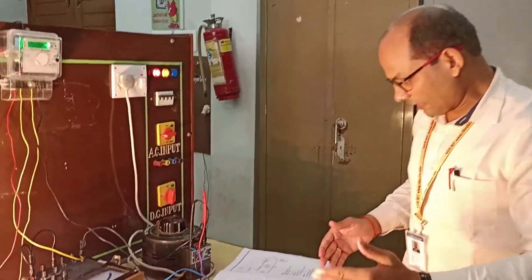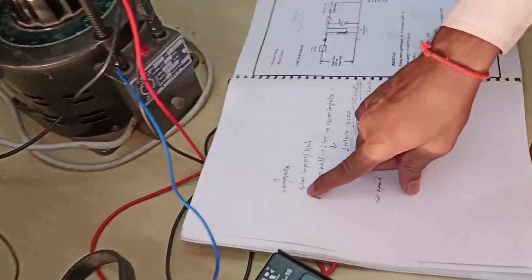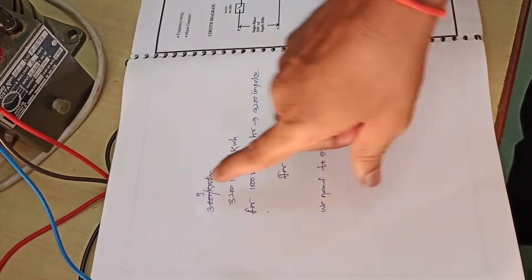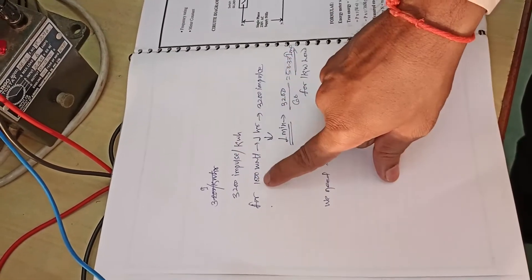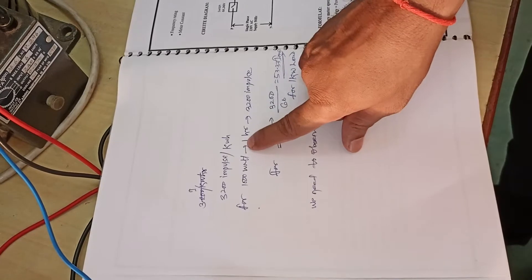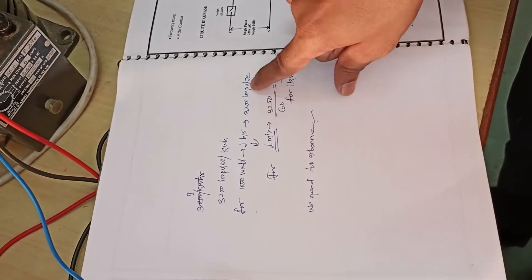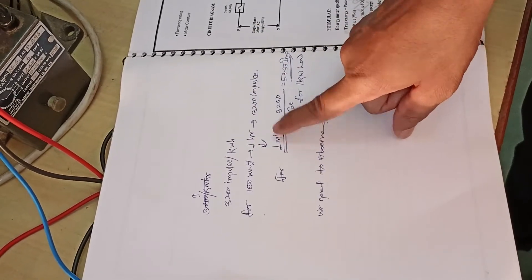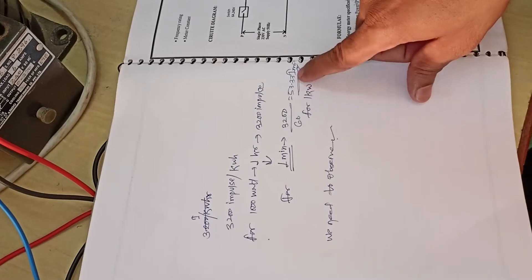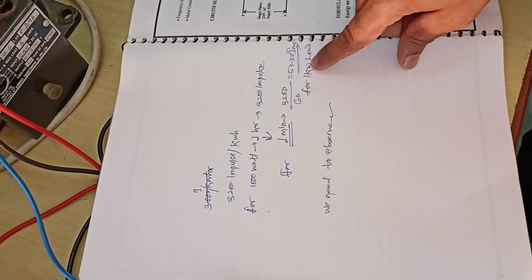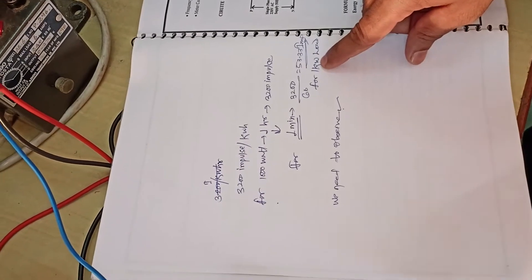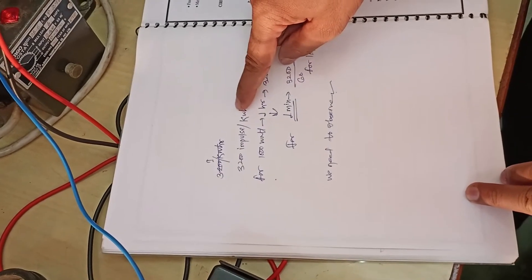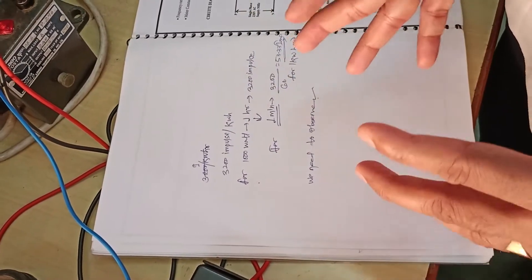Now we need to calculate the error. The reference rating is 3200 impulse per kilowatt hour. I have load of 1000 watt so for 1000 watt used for one hour it should take 3200 blinking. For one minute it will have roughly 53.33 impulse for one kilowatt load.